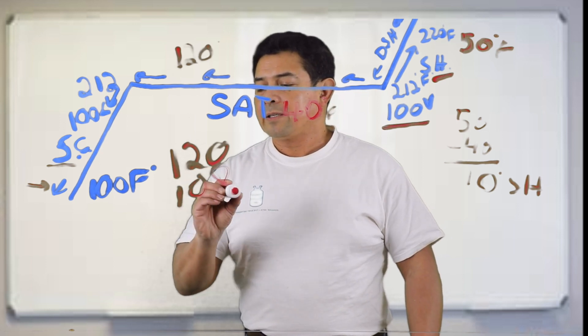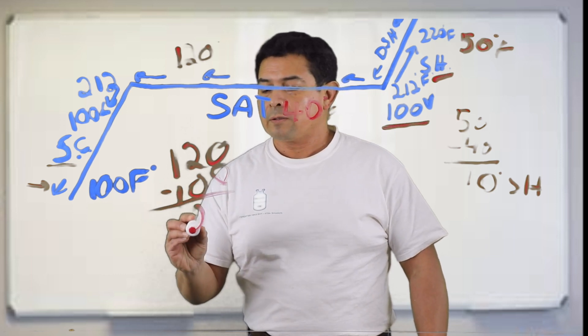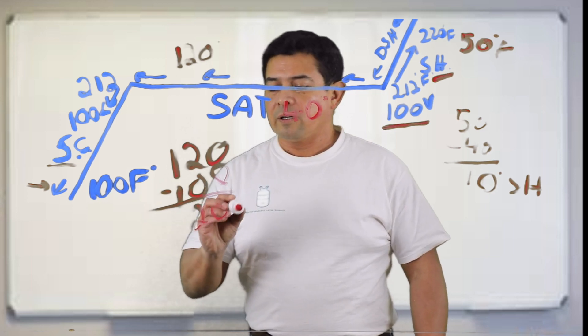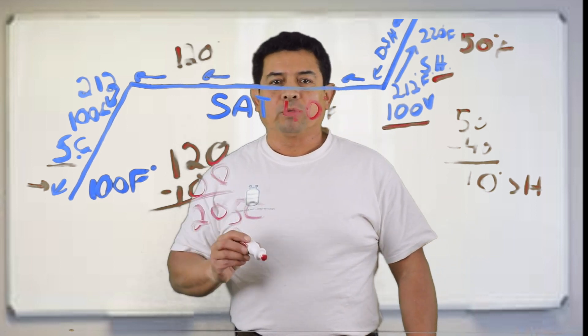And because of that, when we do the math, we subtract, we end up with 20 degrees of subcooling, 20 degrees of subcooling.